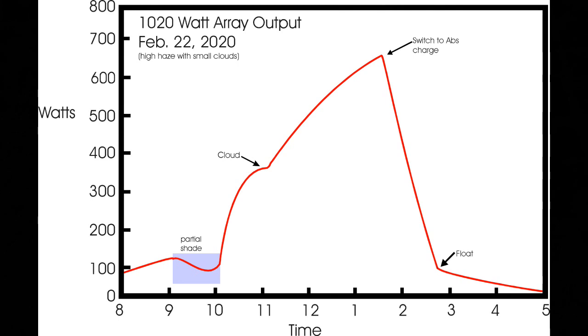In the course of the day, my charge controller told me that my total output was 2,300 watt-hours, which is pretty good. At the time I hit float voltage, when the charge controller thought the batteries were fully charged, I had used about 2,210 watt-hours. My batteries had been drawn down by about 2,000 watt-hours. So it took 2,210 watt-hours to replace 2,000 watt-hours, meaning my charging efficiency is right around 90 percent — pretty good considering I have lead acid batteries. Maximum charge output from the panel into the batteries was about 22 amps.